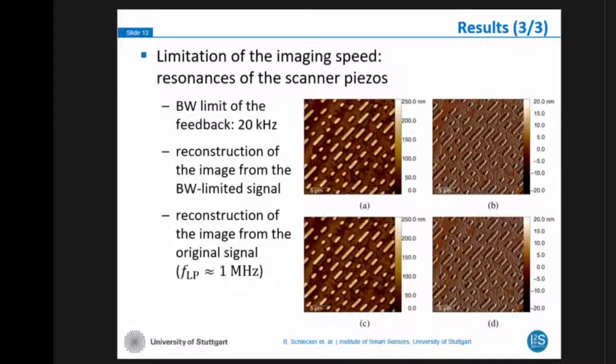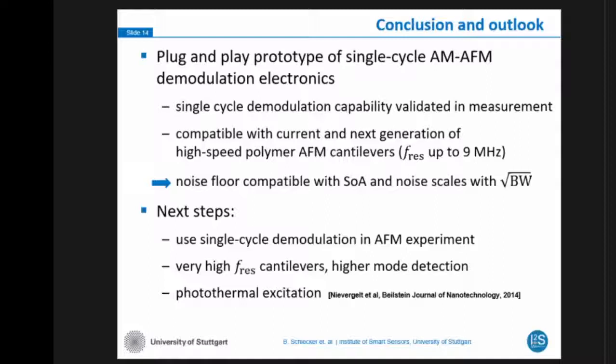In conclusion, we demonstrated a plug-and-play prototype of a single-cycle AM AFM demodulator and demonstrated its capabilities in measurements. The system is ready for current and next generations of high-speed cantilevers up to approximately 9 MHz, and the noise floor is compatible with the state of the art. Our next steps are to use the single-cycle demodulation also for AFM experiments, to use very high resonance frequency cantilevers and higher mode detection, and for that we want to go for photothermal excitation in contrast to the commonly used piezo excitation of the cantilever. Thank you for your attention.